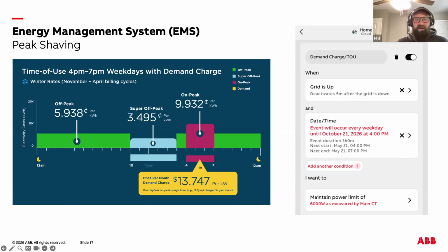So here's an example of peak shaving or demand charge management. We have the APS TOU window for winter rates, and you'll see they have a once per month demand charge of $13.74 per kW during the on-peak hours of 4 to 7 p.m. In this example, an EMS with circuit scheduling and power limiting can be employed to dynamically control loads under a predetermined power limit during the TOU window to mitigate the kW consumed.